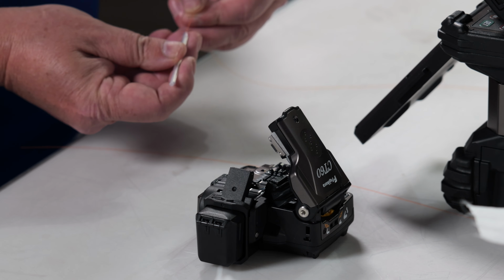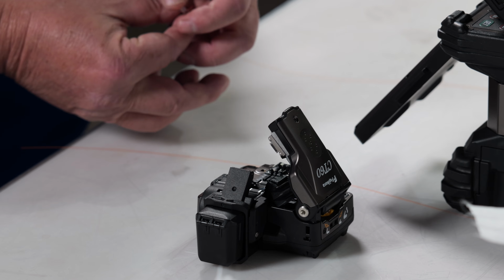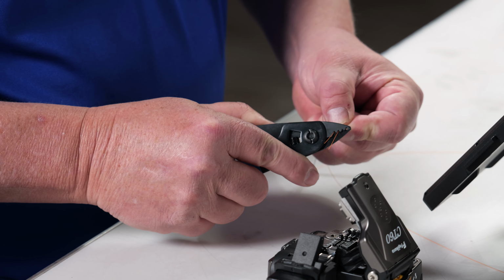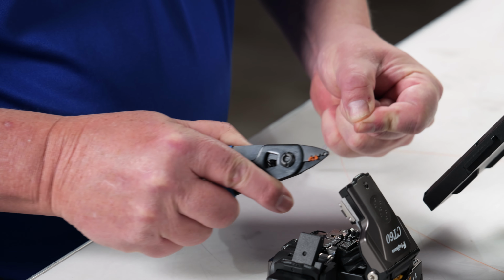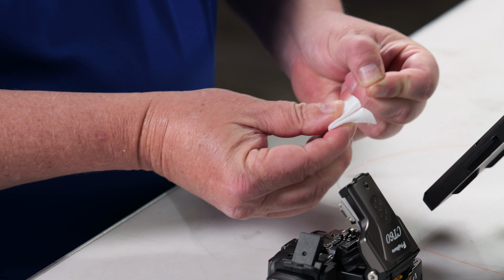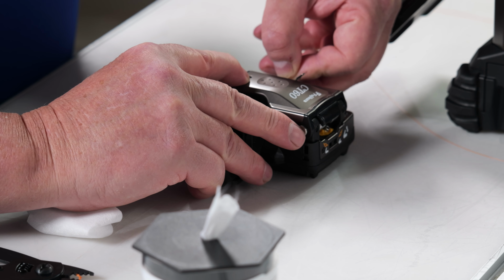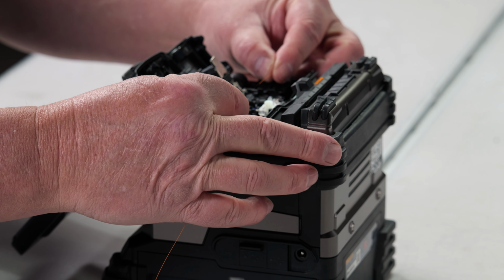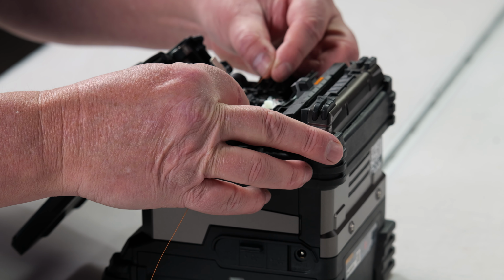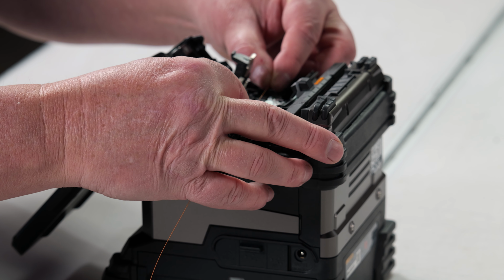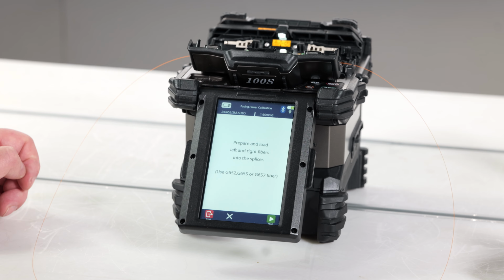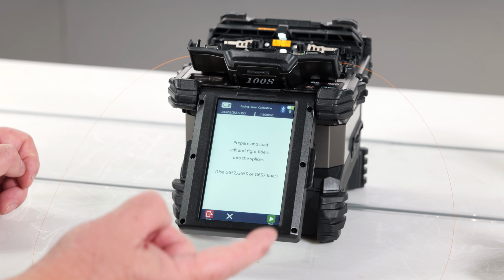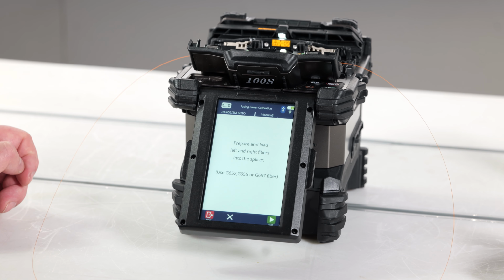Before starting arc calibration, prepare 2 standard fibers just as you are going to perform a splice. Load both prepared fibers into the splicer, ensuring they are positioned correctly before continuing. From the Ready screen, select the arc calibration function using the on-screen shortcut and menu option. Once the fibers are loaded, start the arc calibration process.